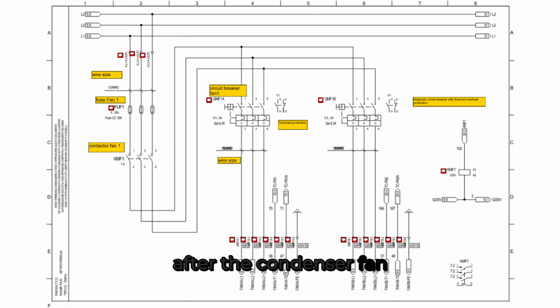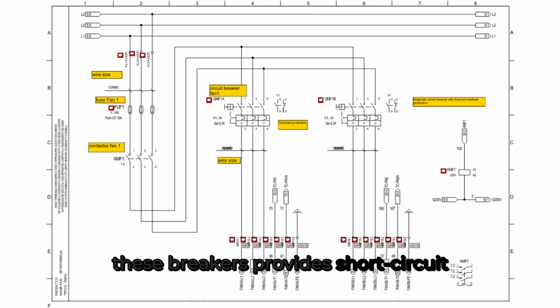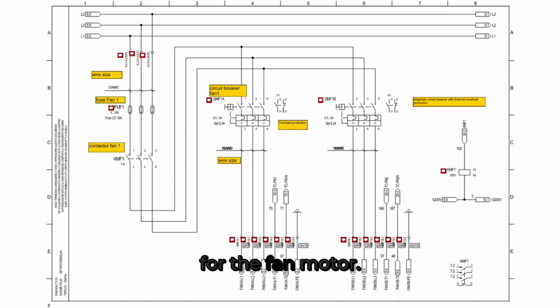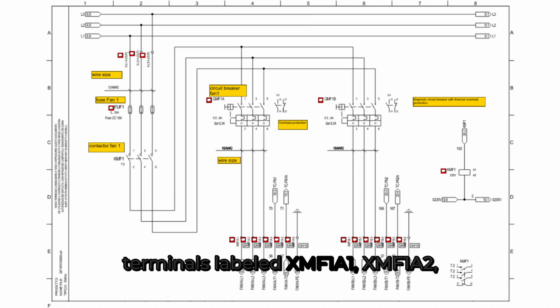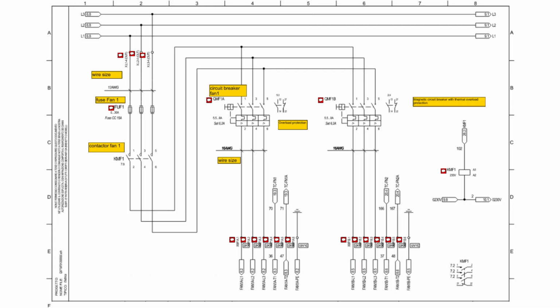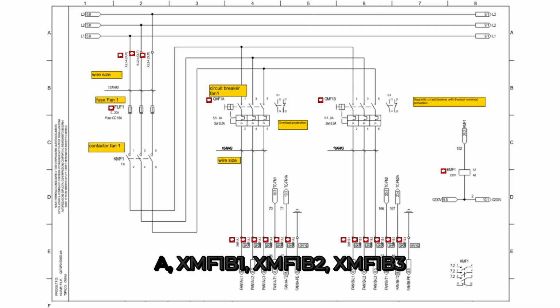After the condenser fan contactor, the power wire is tapped off for two magnetic circuit breakers labeled QMF1A and QMF1B. Each of these breakers provides short circuit and thermal overload protection for the fan motor. They are set at 6.2 amps. The outgoing wires from each circuit breaker are 16 AWG, supplying the fan motor terminals labeled XMF1A1, XMF1A2, XMF1A3 for fan motor A, and XMF1B1, XMF1B2, XMF1B3 for fan motor B.